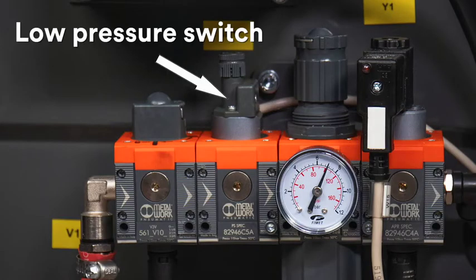The low pressure switch closes at pressures at or above the predetermined value and opens for lower pressures. If the pressure is too low, the PLC will be signaled and a fault will occur. Lifting and rotating clockwise increases the minimum pressure required for machine operation. Rotating counterclockwise decreases the required pressure. Once set, push downward to lock into position. Refer to your instructions and parts list owner's manual for the recommended setting.